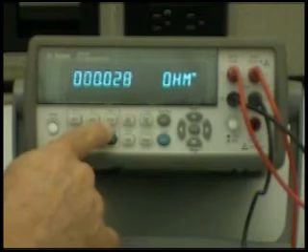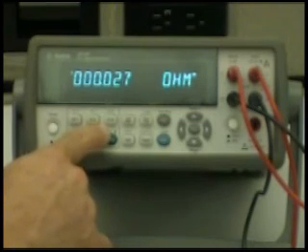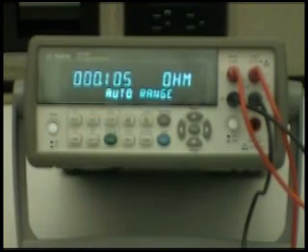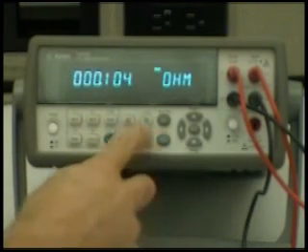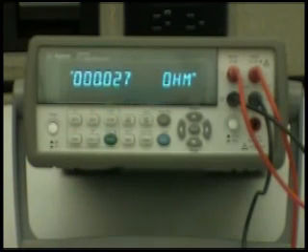I can just toggle back and forth between 2-wire ohms and 4-wire ohms. Go back to 2-wire ohms. You can see we're back up again about 100 milliohms, shift 4-wire ohms, and now we're back to about 27-28 milliohms. So it's a very convenient way of negating the lead resistance when you're trying to make low resistance measurements. So this concludes our short video describing how to make 4-wire ohm measurements.